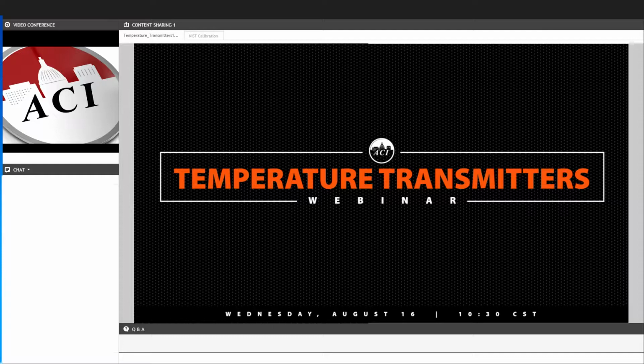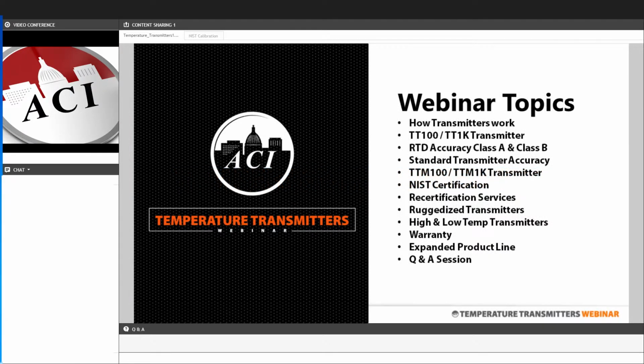Today, in the temperature transmitter product line, we're going to talk about how transmitters work and compare them to some of the more commonly used thermistors and RTDs. We're going to talk about the difference between Class A and Class B RTDs and how they can make a difference or impact the overall transmitter accuracy. We'll then go into our NIST certification process and recertification services.